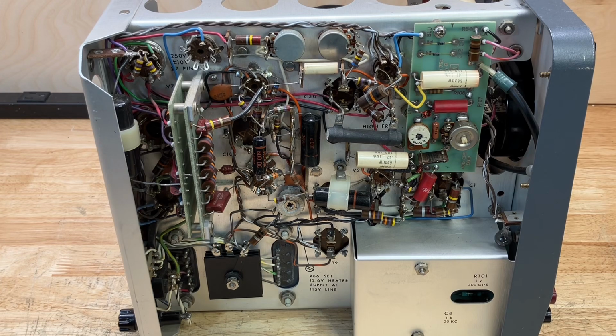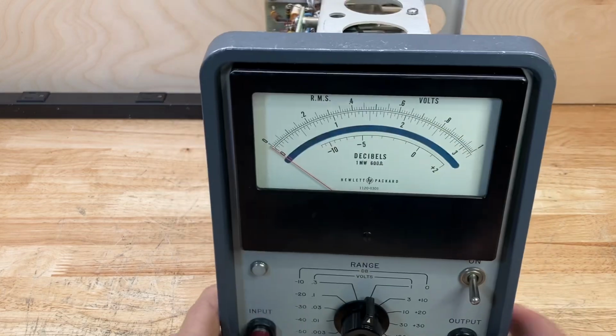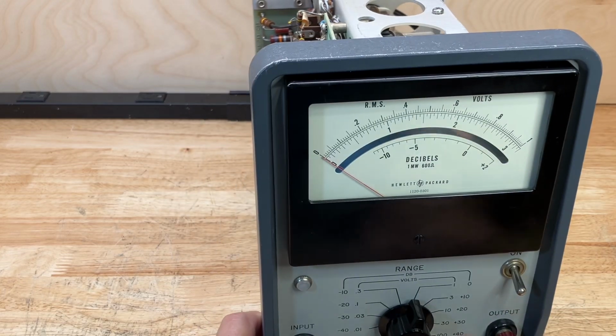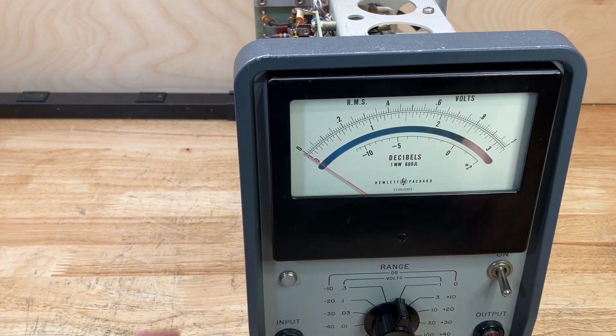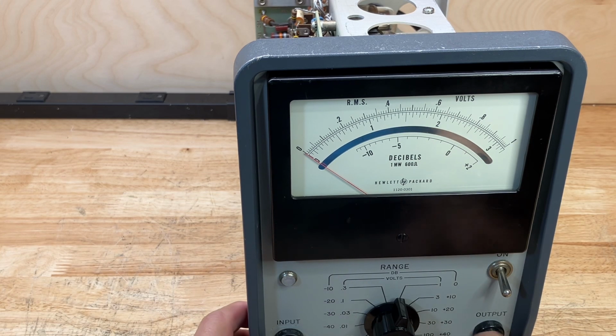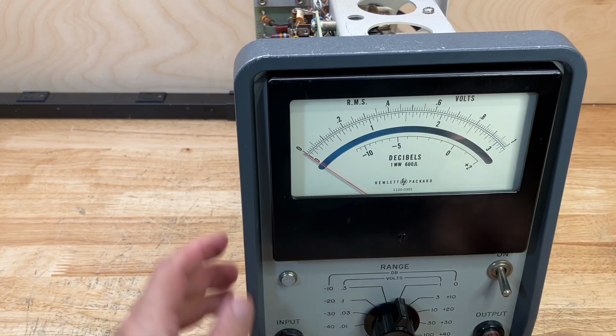All right, so I have completed the realignment calibration procedure for this unit off camera because it's long and boring and kind of tedious, but I wanted to show you the process and show you where the adjustment points are inside the instrument so that you can see what the process was that I went through. Basically, we start by calibrating it on the 1 millivolt range. So we dial this all the way down. It's turned off now and unplugged, but I just want to show you how it works, how we do it. So it's set to the 1 millivolt range.